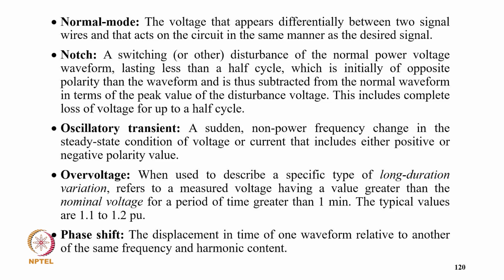Notch: a switching or other disturbance of the normal power voltage waveform lasting less than half a cycle, which is initially of opposite polarity to the waveform, and is thus subtracted from the normal waveform in terms of the peak value of the disturbance voltage. This includes complete loss of the voltage for up to half a cycle. Oscillatory transient: a sudden, nonpower frequency change in the steady state condition of a voltage or current that includes both positive and negative polarity values.